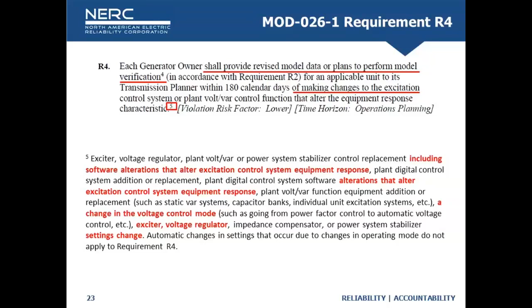And there's a footnote there, and I've highlighted in red, including software alterations that alter excitation control system equipment response, a change in the voltage control mode, or exciter voltage regulator, reactive power voltage control settings changes. So when you go in and you change a large disturbance or a small disturbance setting or a control mode, or anything that could change the response of that resource to a fault or a step change in voltage, updated model or revised model data needs to be provided, or you need to perform re-verification per the standard. And I don't think that's happening in a lot of cases. So there is potential compliance risk there on the generation side.